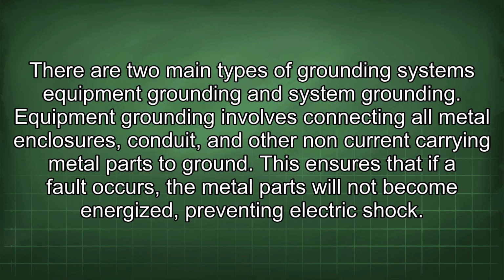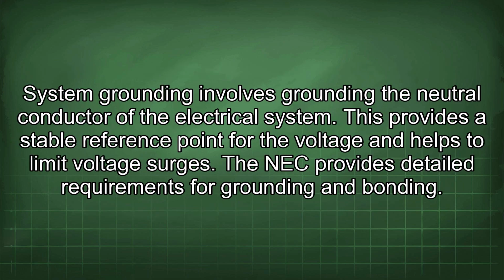There are two main types of grounding systems: equipment grounding and system grounding. Equipment grounding involves connecting all metal enclosures, conduit, and other non-current carrying metal parts to ground. This ensures that if a fault occurs, the metal parts will not become energized, preventing electric shock. System grounding involves grounding the neutral conductor of the electrical system. This provides a stable reference point for the voltage and helps to limit voltage surges.